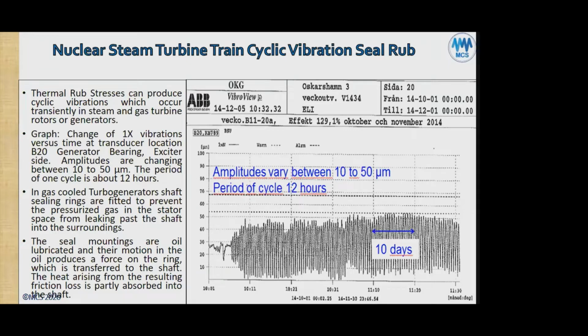The period of one cycle is about 12 hours. In gas-cooled turbo generators, shaft sealing rings are fitted to prevent the hydrogen gas in the stator space from leaking past the shaft into the surroundings. So you have to seal it inside. We don't want to lose the hydrogen, and it'll also cause a fire.